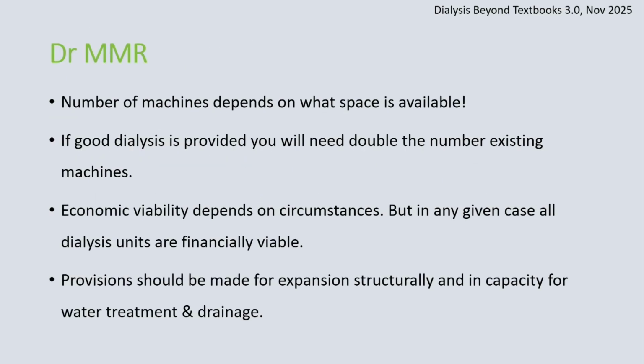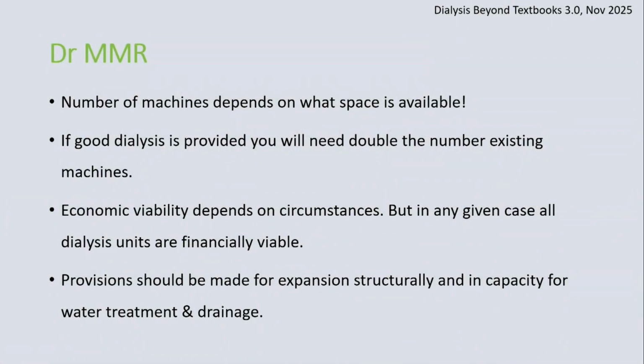Obviously, your number of machines will depend on what is the space you have available. So, each machine would need at least about 100 square feet. The point is the space is needed not only for the bed or the chair, the dialysis machine itself, and one attendant sitting there. And in an emergency, you should be able to wheel the cart in all around the bed, and you should have spare plugs and things like that. This is extremely well described in the setting up of the haemodialysis unit, which was first written for the Indian Society of Nephrology in 2010 and was completely revised in 2020. In fact, one of the colleagues, Dr. Gomati, was with us in writing that chapter on setting up of the dialysis unit.